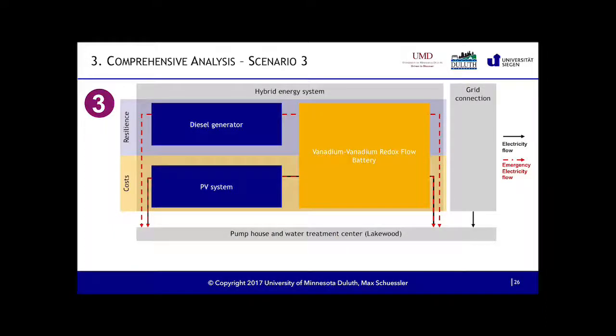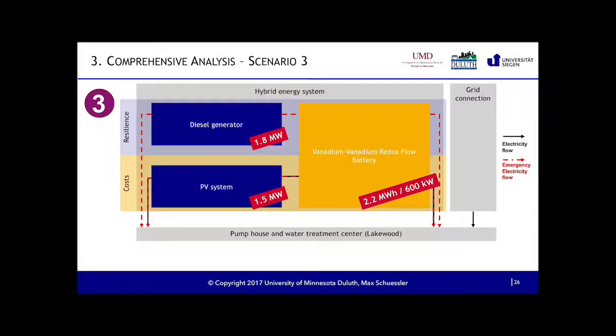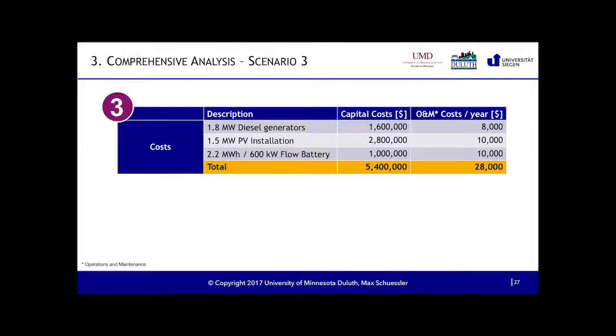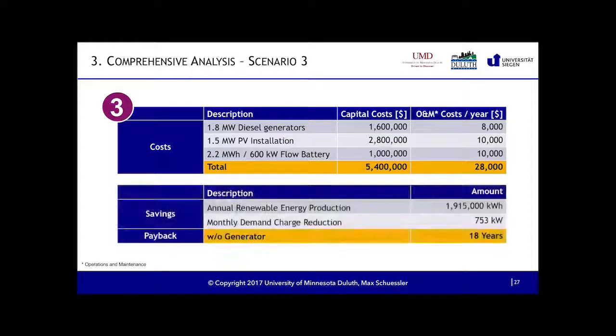And now my third scenario, I actually use my battery in a whole hybrid way to its maximum extent, hopefully. And I would have only $5.4 million of investment up front, which is lower than scenario 2, because I can downscale my generator to 1.8 megawatt instead of 2.5 megawatt, because I can use the power of my battery to offset some of the surge load I have to cover when my pumps start turning. And then for my savings, I'll be able to offset all my energy and peak shave down to 750 kW, so we don't have to pay for as peak demand per month, and this would also lead to 18 years of payback.